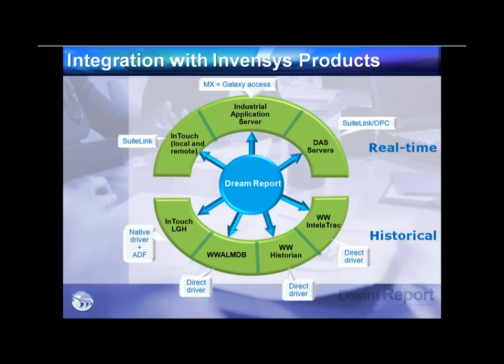There is a native connector for the Wonderware Alarm Logger database. Many customers use Wonderware Alarm Logger with AppServer or InTouch to record alarms and events into a SQL database, but DreamReport makes it very easy to connect to that database without writing any SQL queries — choosing alarm tables, fields like alarm time, duration, acknowledge time, and operator — to create alarm and event reports with Pareto charts or data grids.